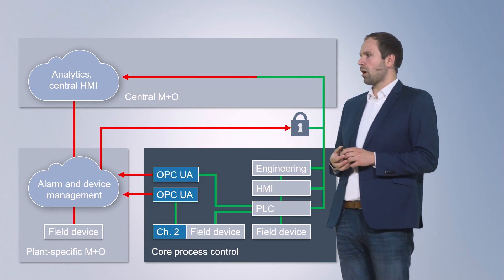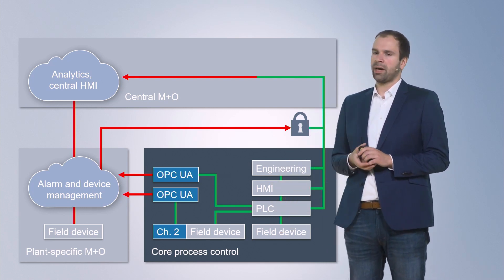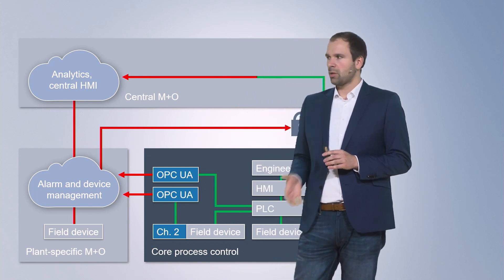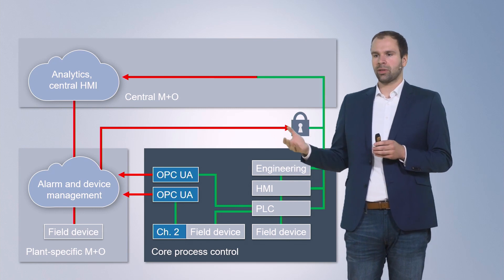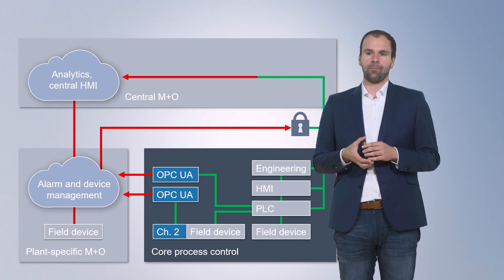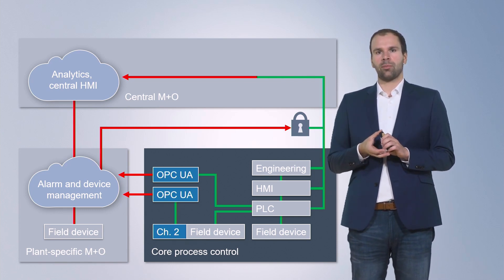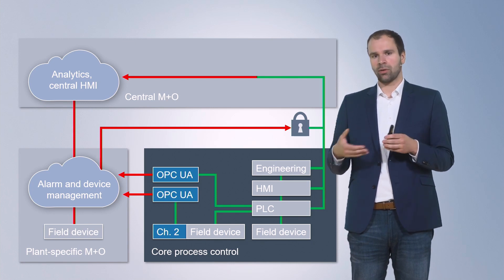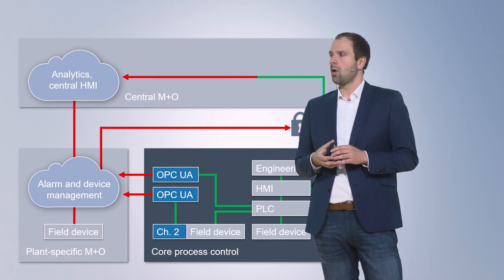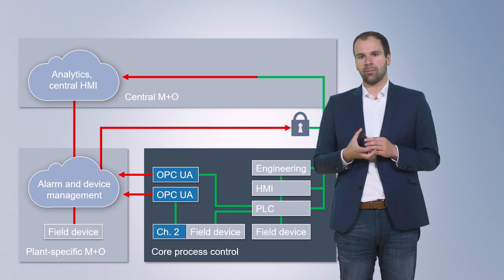Looking at the NOA architecture, all existing infrastructure — the existing DCS system, controllers, and so on — remains untouched. We simply add the NOA Edge device, represented by the blue blocks. The second channel connects to the field device, and we can also grab data from the existing PLC. All of that information is made available through the OPC UA server, which then publishes data for device management or optimization. Higher-level systems can run analytics locally on the plant or in a central M+O system that aggregates data from different locations of the same operator.